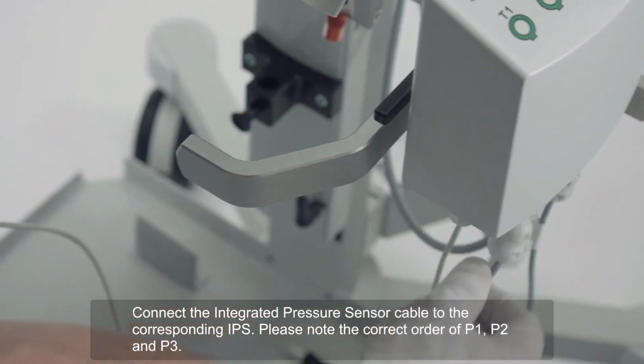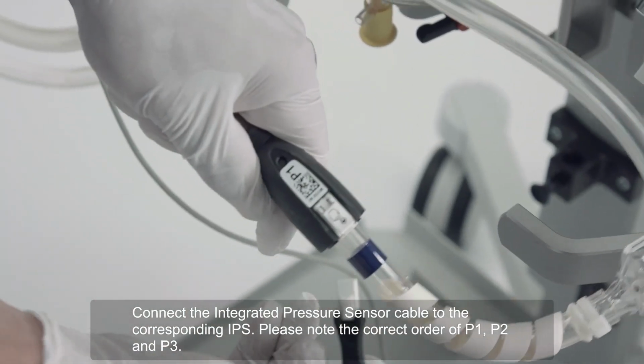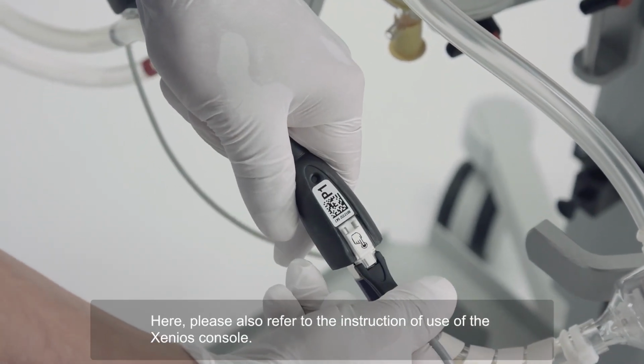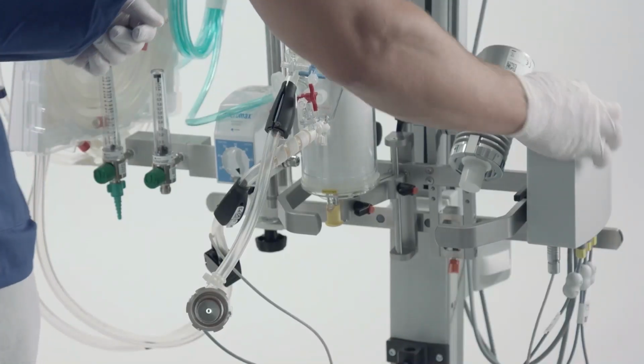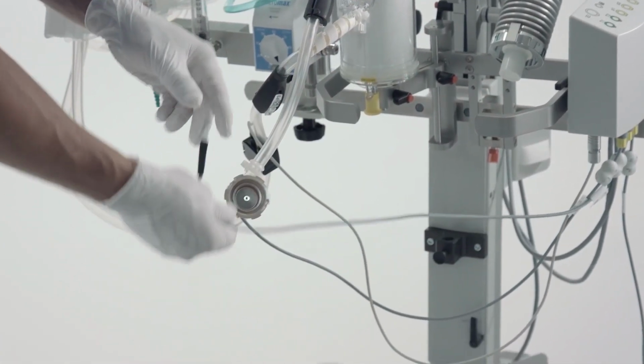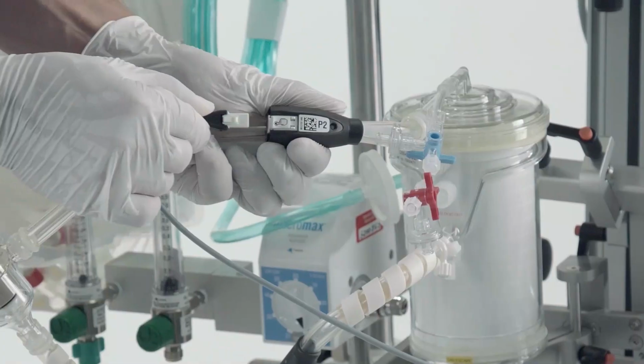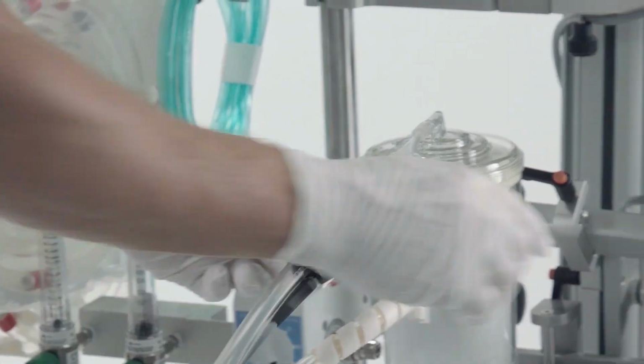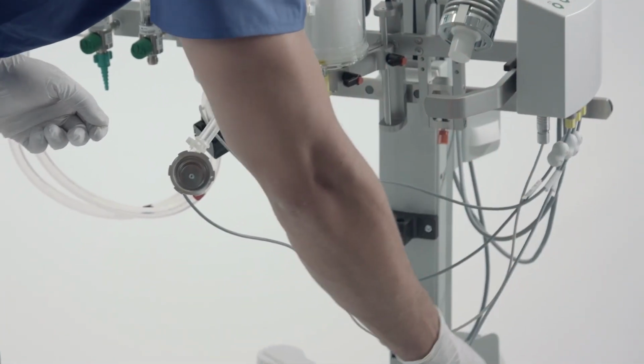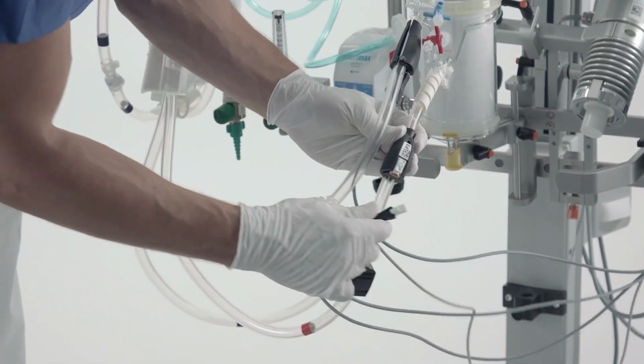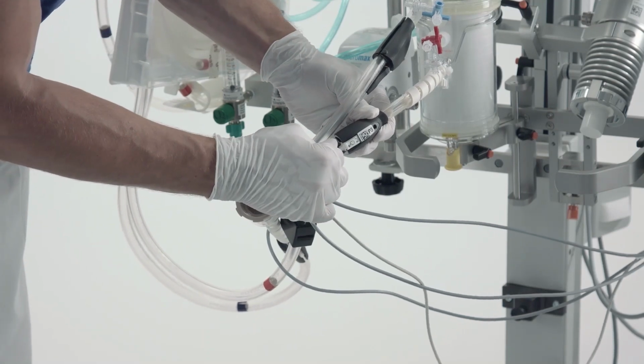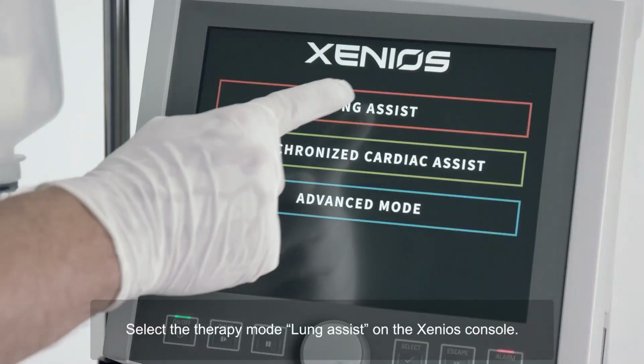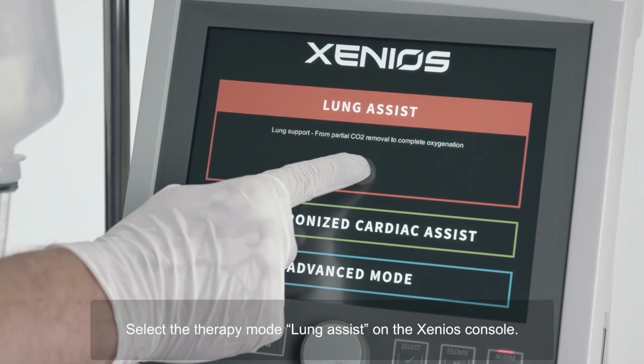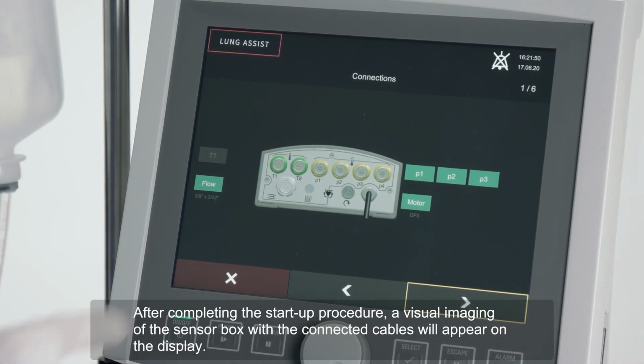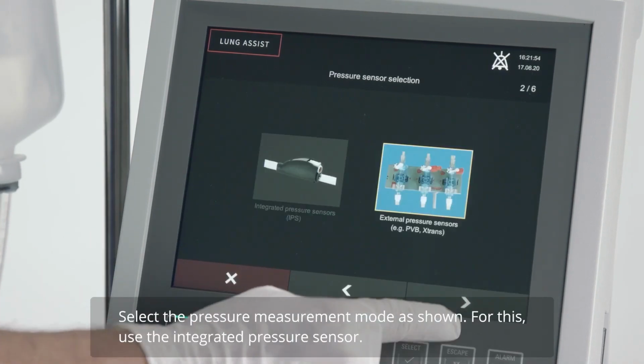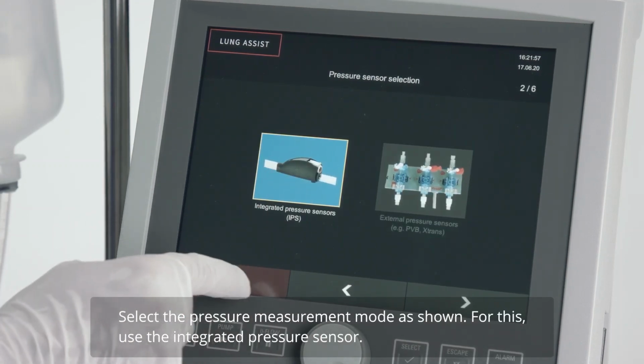Connect the integrated pressure sensor cable to the corresponding IPS. Please note the correct order of P1, P2, and P3. Here, please also refer to the instruction of use of the Xenios console. Select the therapy mode Lung Assist on the Xenios console. After completing the startup procedure, a visual imaging of the sensor box with the connected cables will appear on the display. Select the pressure measurement mode as shown. For this, use the integrated pressure sensor.